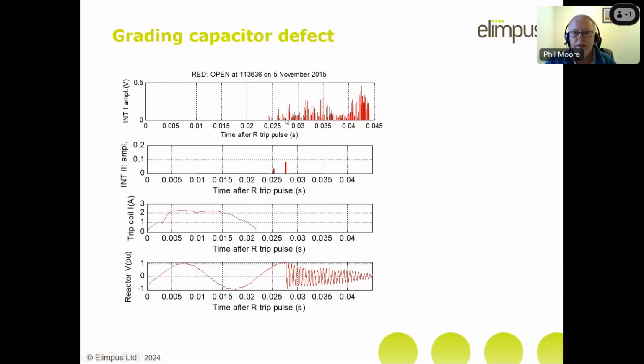This is arc instability. There's slightly more on interrupter 1, a little train of them there. But you can see that after the arc's gone out, on interrupter 1, we get these large emissions of impulses coming from interrupter 1, whichever one that was. And that was actually due, well, we didn't realise it initially, that was due to the grading capacitor.